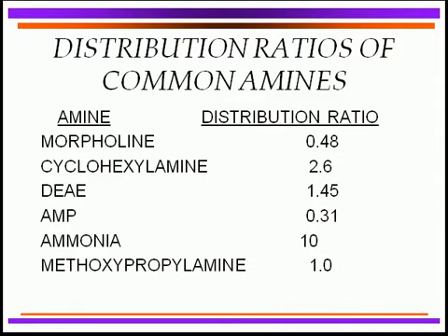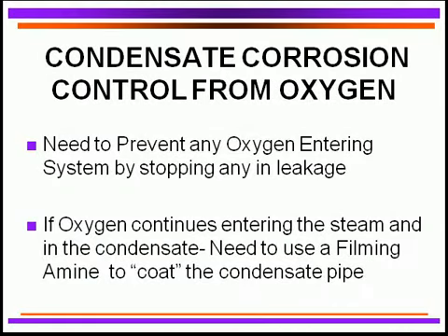There are a variety of different amines that can be utilized. If you do have oxygen corrosion in your condensate, the first thing to do is stop the oxygen from getting into your system. It won't come in through the boiler because oxygen scavengers handle that. Where does oxygen enter the condensate system? When steam condenses, it pulls a vacuum, and any leakage points in that condensate line can pull oxygen in. The best approach is to stop any in-leakage of oxygen.